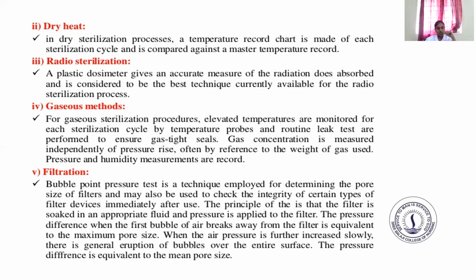And gaseous method. For gaseous sterilization procedure, elevated temperatures are monitored for each sterilization cycle by temperature probes and routine leak tests are performed to ensure gas tight seals. Gas concentration is measured independently of pressure rise, often by reference to the weight of gas used. Pressure and humidity measurements are recorded.